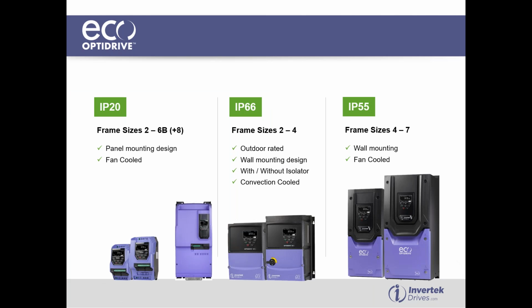So the IP20, as I mentioned earlier, we've got a new frame size 8, which is also available on IP20, and that's designed to be mounted into a control panel, and these are fan-cooled units. So the space required to keep the airflow in the cabinet is in the manual. It's very simple. Just have a space above and below the unit just to make sure that the airflow is not blocked, just for cooling.